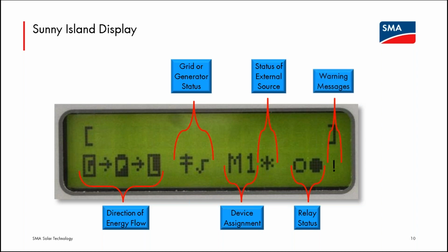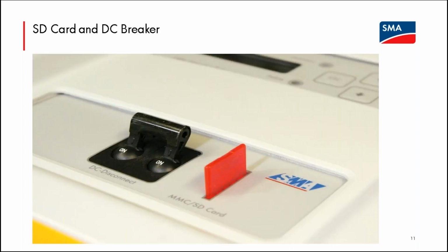The DC breaker, it's labeled as DC disconnect, you may see in this diagram. That is completely incorrect. This should be considered simply an on-off switch for the Sunny Island. Between the Sunny Island and its battery bank, there needs to be an external DC circuit breaker or fuse connection. If the DC circuit breaker, the one shown in this picture on the front of the Sunny Island, is in the off position, there is still voltage at certain spots on the circuitry inside. So this should be considered simply an on-off switch for the Sunny Island.